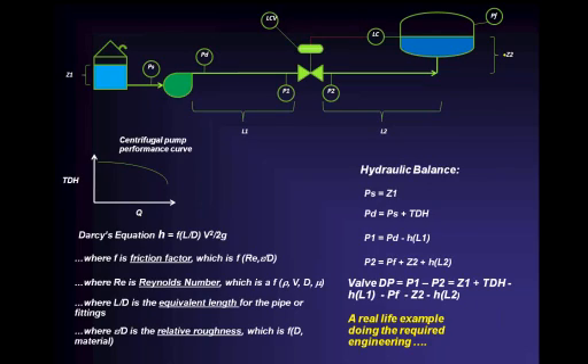I was asked to increase the capacity of a reheat spray valve, and we did this analysis. I actually walked off all the pipe, counted all the elbows, the T's, every fitting, run T's, branch T's. Are they short radius elbows, long radius elbows? All of these have different K factors. When you sum up all the K factors, then you can do your head loss, your Darcy equation.